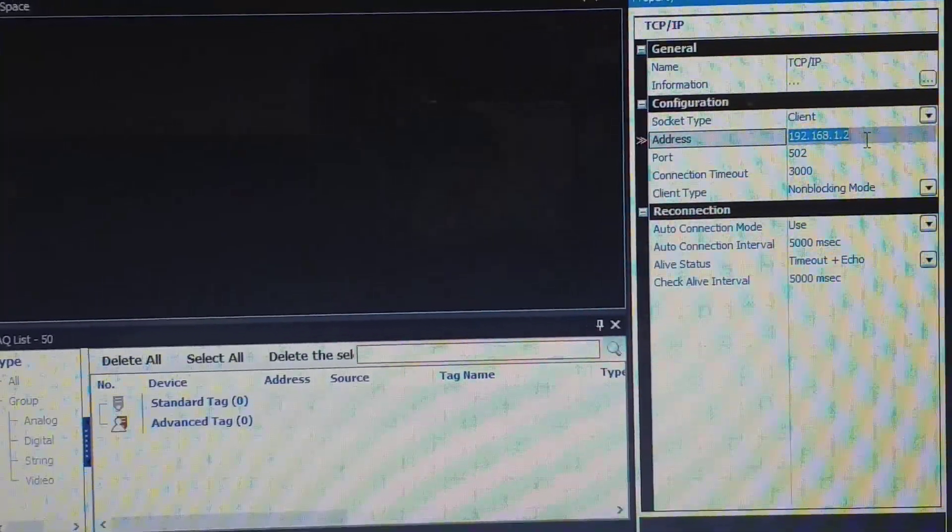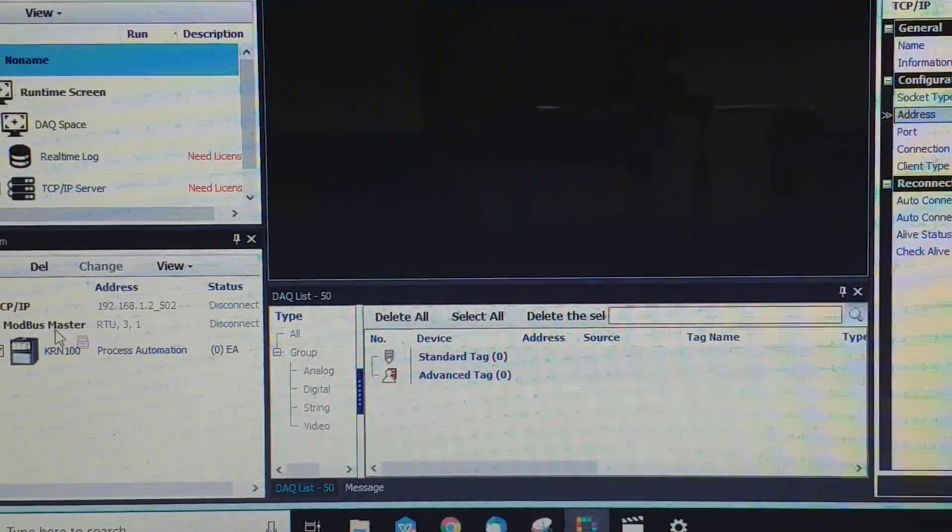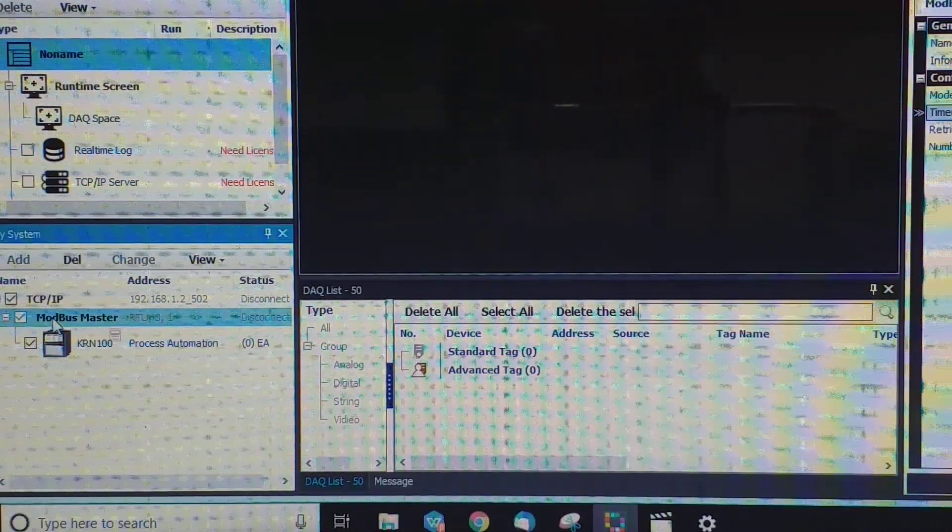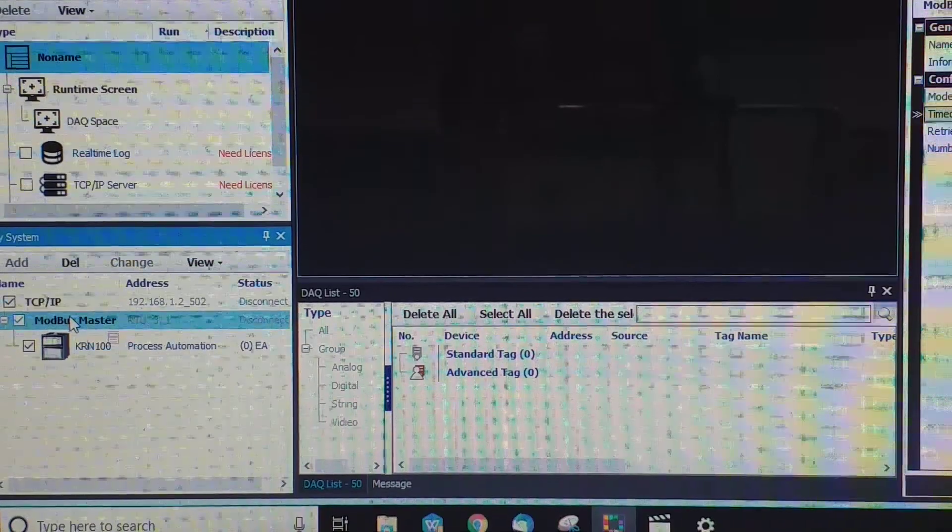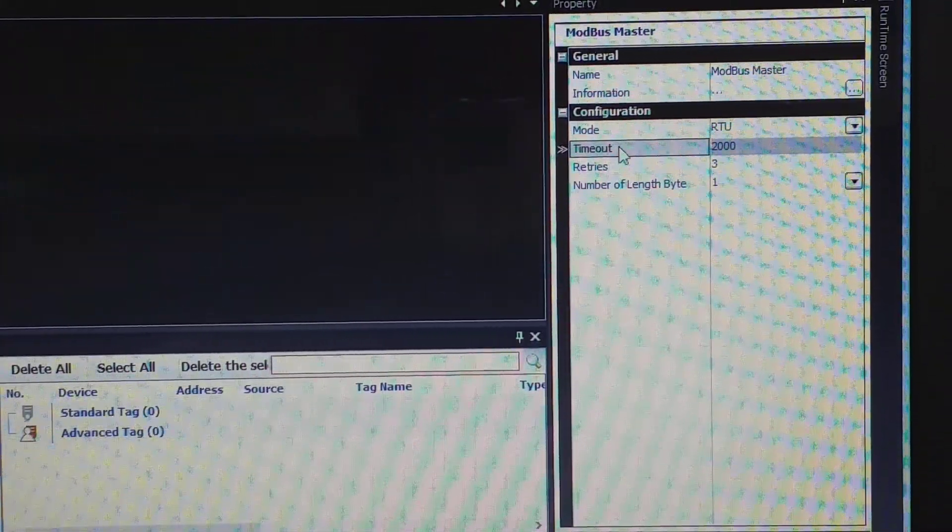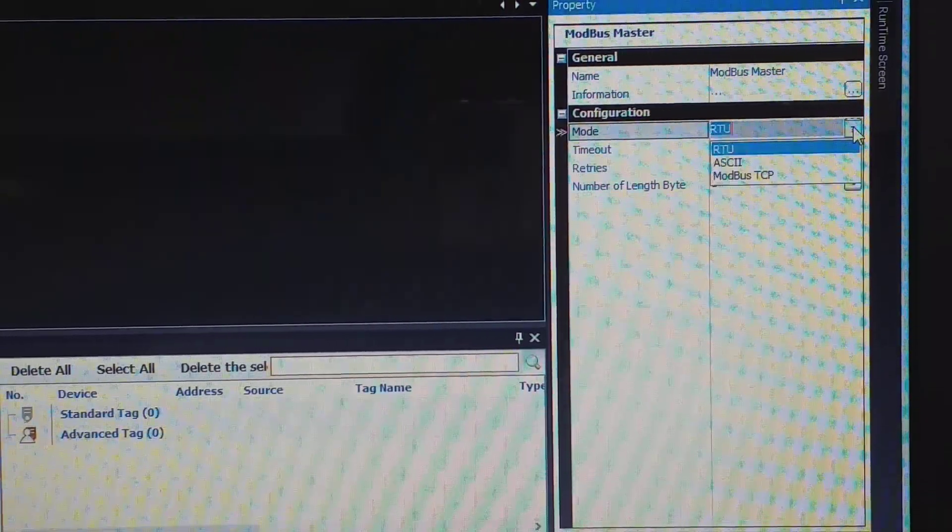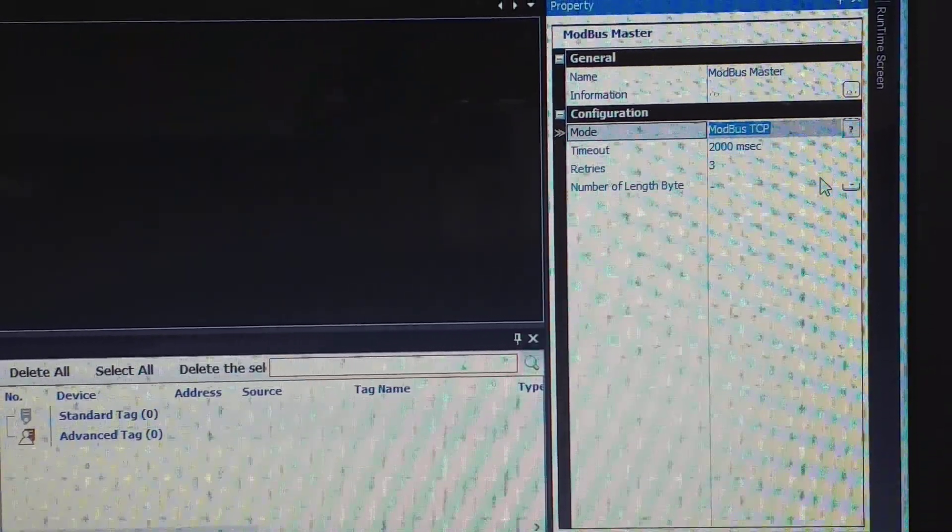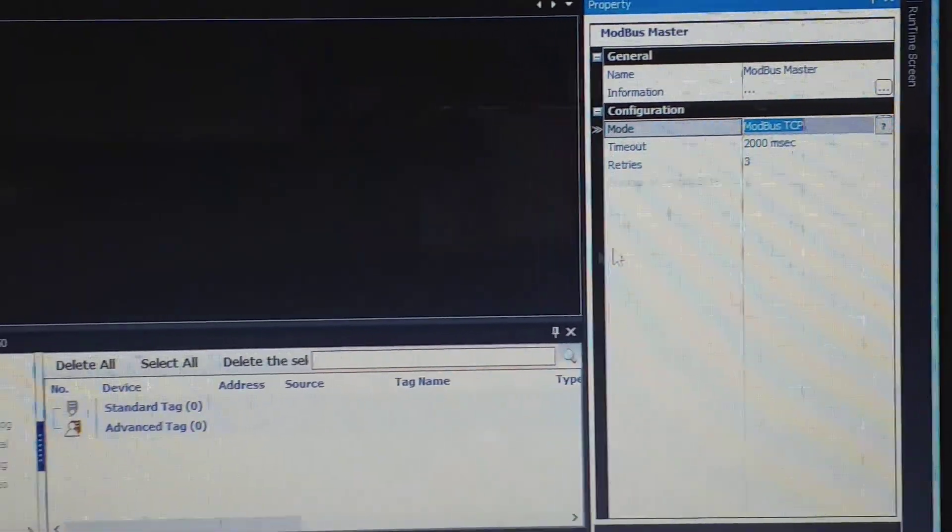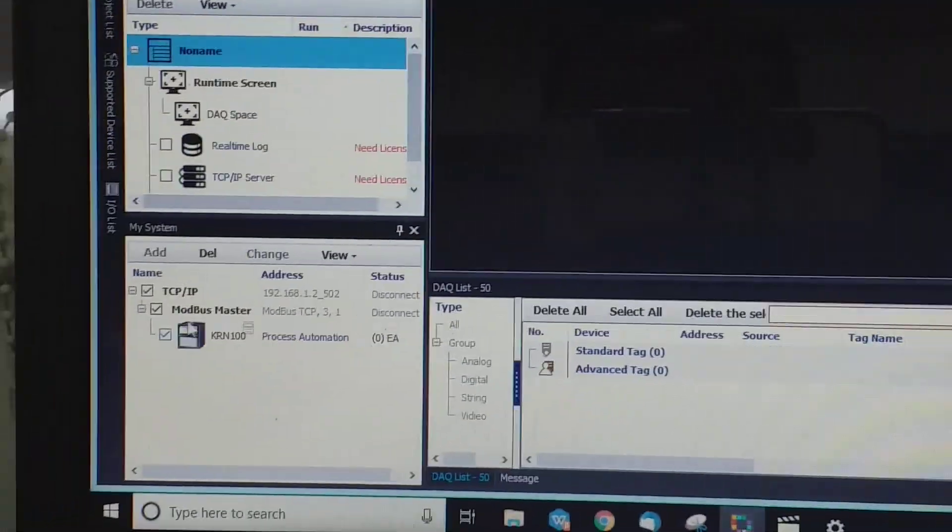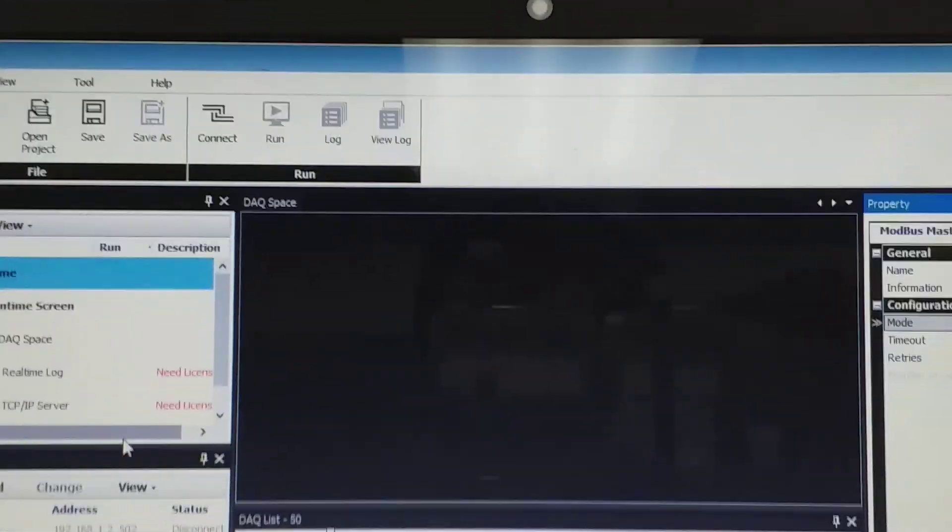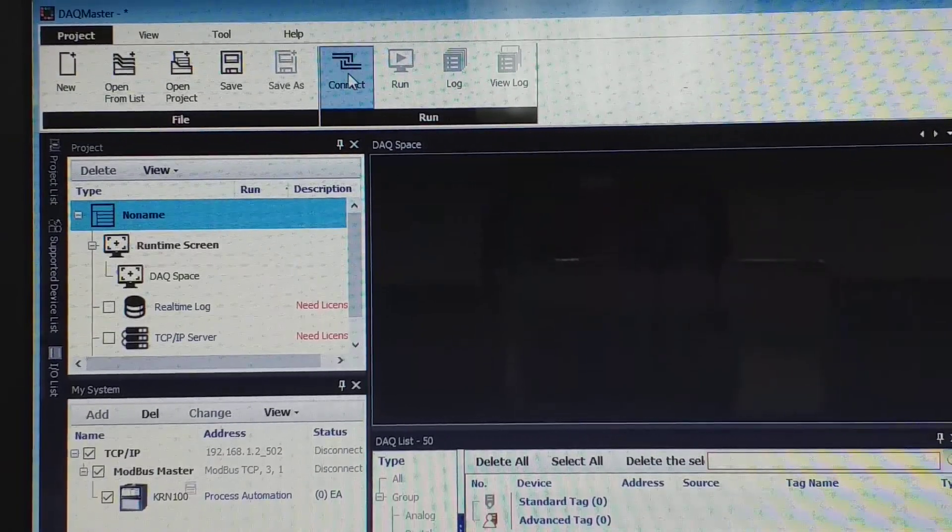Okay, now you go to Modbus Master, you click here. Before that you click there, okay? Modbus Master you click. So you change it, the mode RTU to Modbus TCP. You use as a Modbus TCP, done. Just change and next you just press connect.